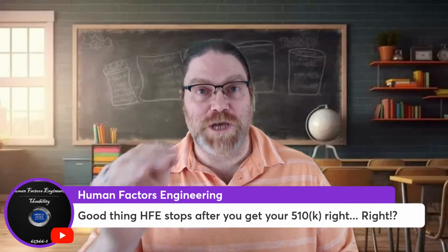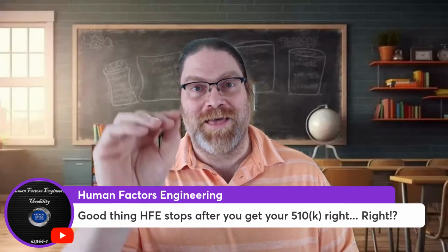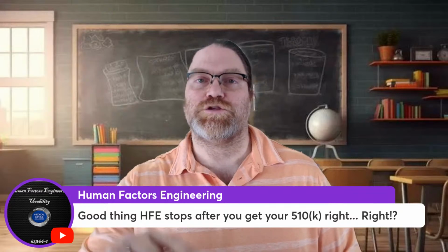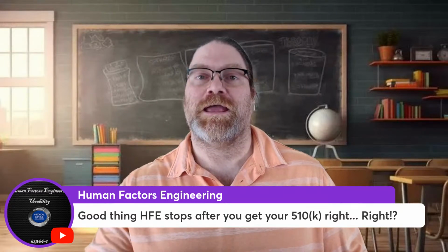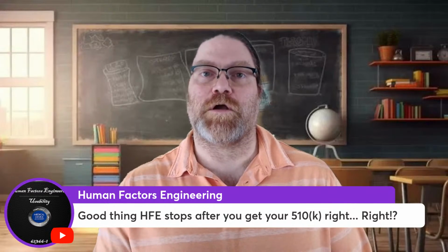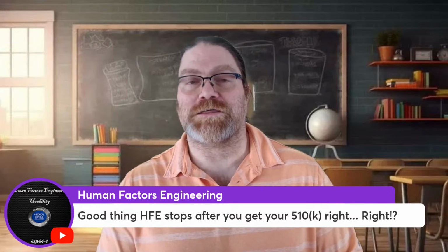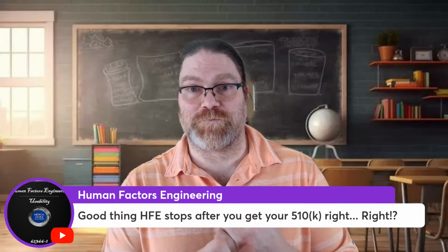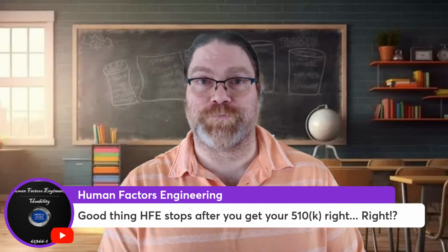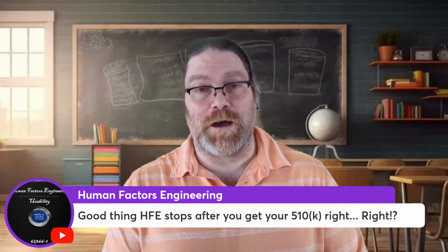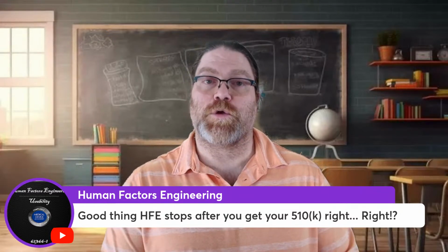Absolutely not. Just like all your other risk management activities, that last step, clause 10 in ISO 14971, is you do post-market and post-production data collection to go back and figure out what things aren't working well. That goes for human factors as well. You're required in clause 8.2.1 of 13485 to do post-market surveillance. You're required to have a cybersecurity post-market surveillance plan. You're required to review complaints and identify bugs in your product, if it's software. And you're required to review any complaints in general and implement CAPAs if your investigation determines that's what's needed.